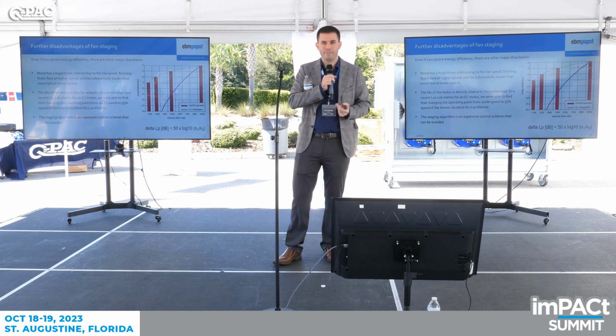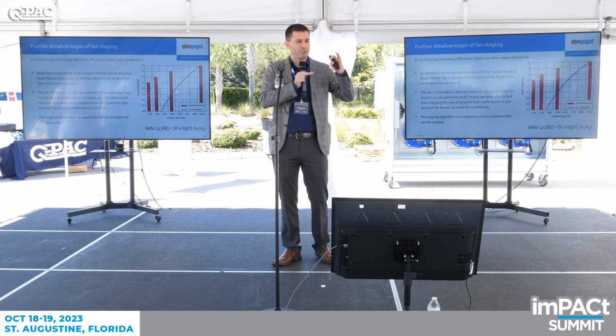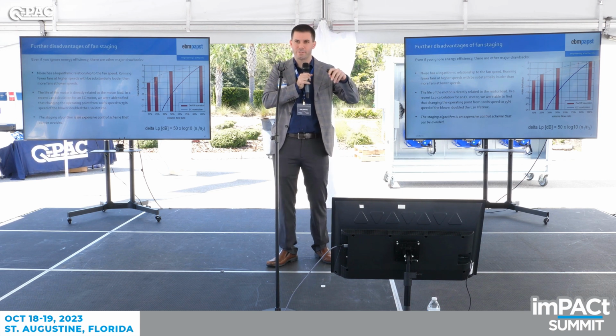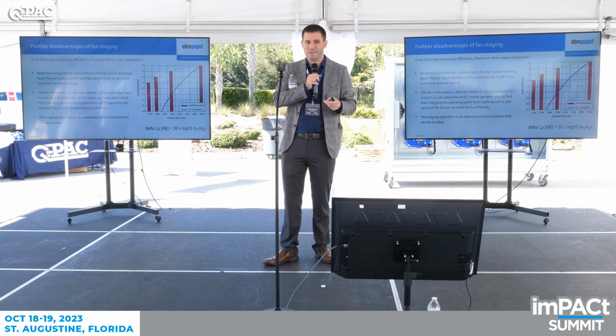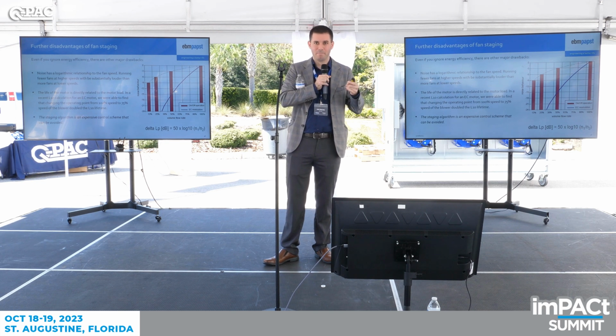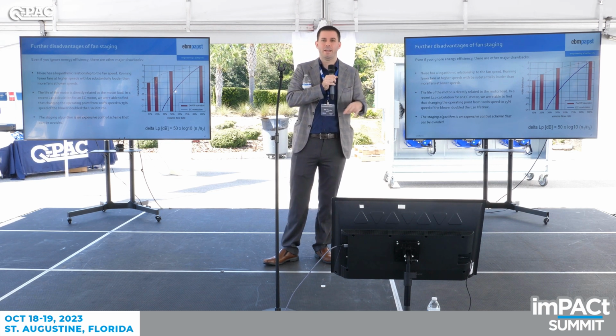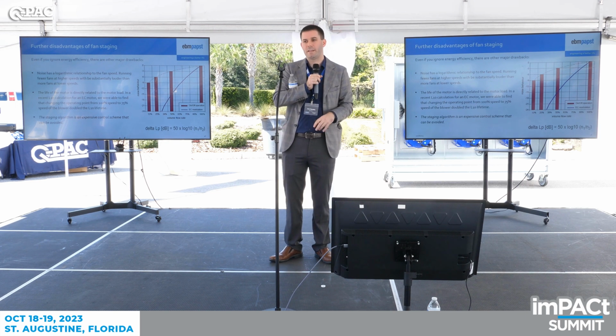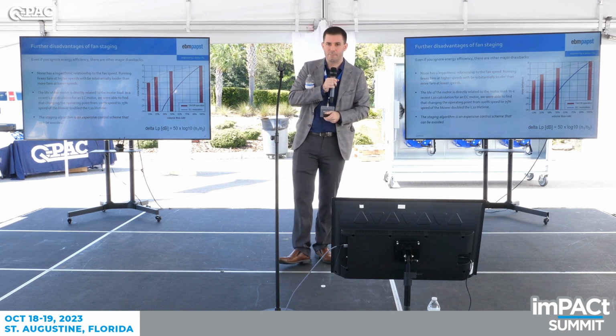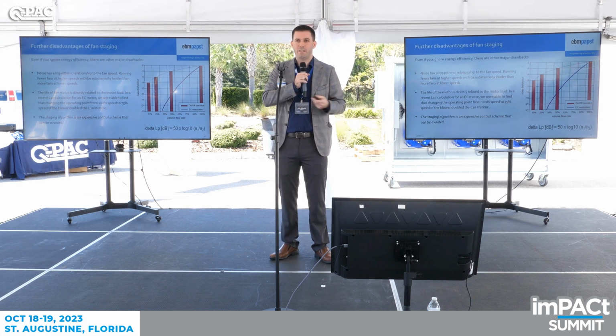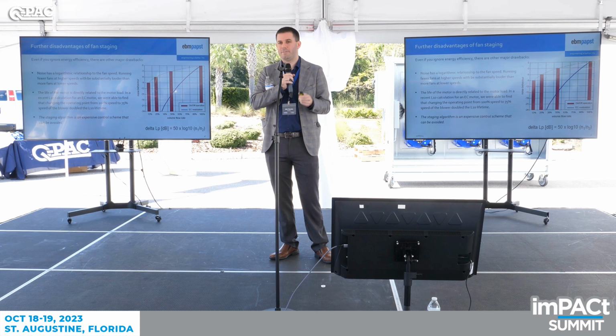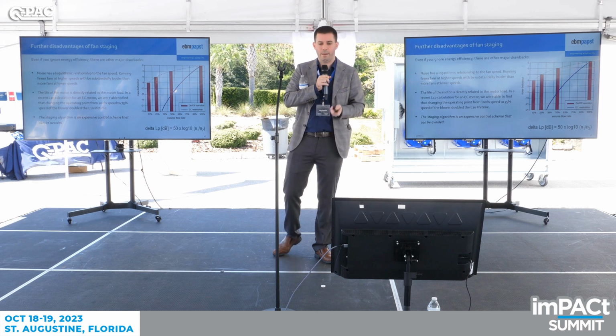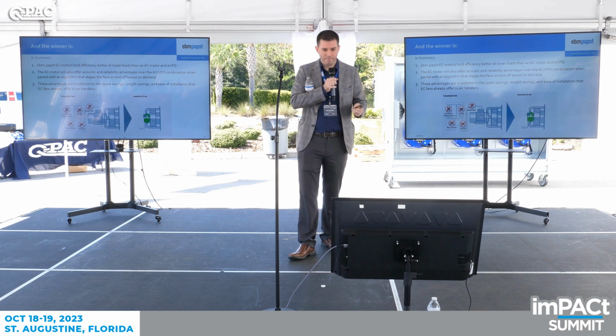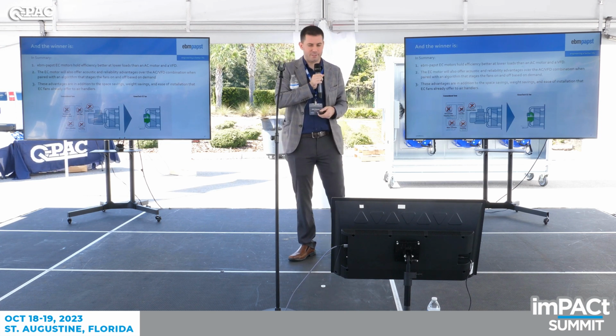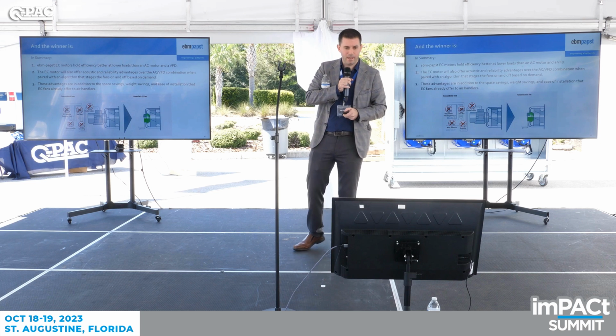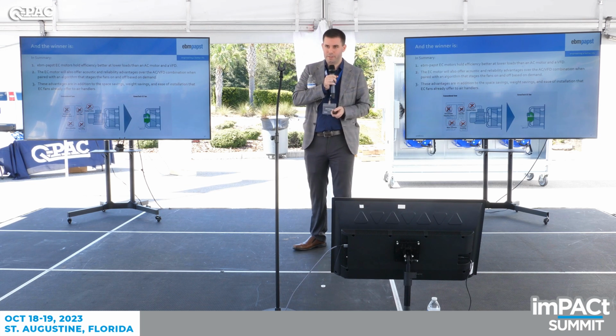Now, one of the reasons it might make sense with an AC VFD to do this staging and turning on and off, like maybe you turn off one of them and keep the others high, is that at 50% speed, we saw there's a big efficiency gap. So they don't want to run at 50% speed because there are inefficiencies there. They want to keep those fans running at the higher speeds as much as possible in order to keep that efficiency high. But with the EC motor, you don't have to. Now you're going to get the benefits of lower acoustics, longer life, lower power. So in summary, the EC fan holds its efficiency much better, just technology-wise, at lower speeds. It's also going to offer you an acoustic and reliability benefit.